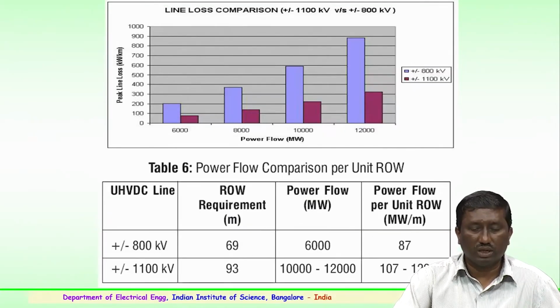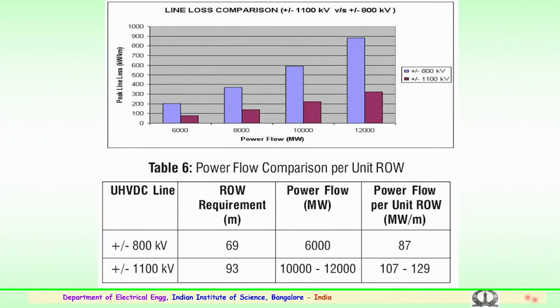This gives the line losses comparison for both 800 kV and 1100 kV DC. You can very clearly see, for transmission of 6,000 megawatts, the comparison between 800 and 1100 HVDC lines. This is the peak line losses, in kilowatt per kilometer on the y axis, and the x axis is power flow in megawatts. So, a very clear comparison is shown here for 1100 and 800 kV. The blue is for 800 kV and the red is for 1100 kV.